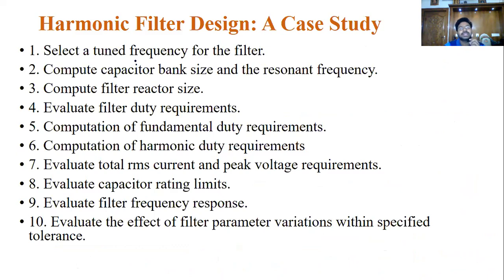First of all, select the frequency of the filter. What is the frequency of the filter? The tuned frequency is the order of harmonic you are going to eliminate: second order, third order, fourth order, fifth order, and so on. You tune the filter to that order, so this order is important.